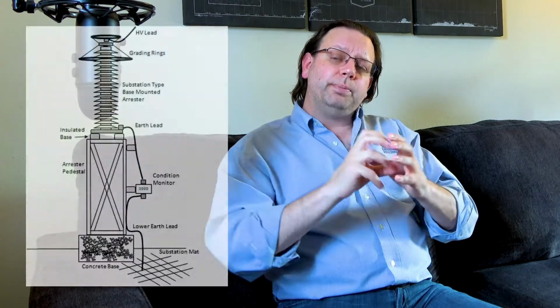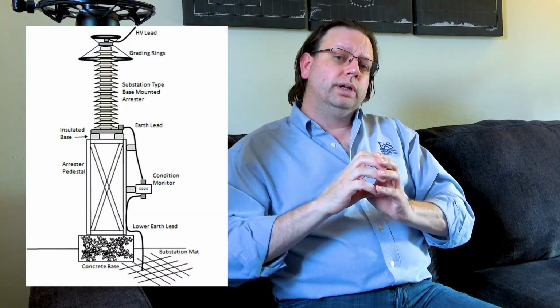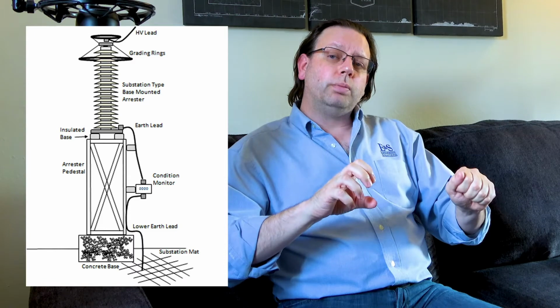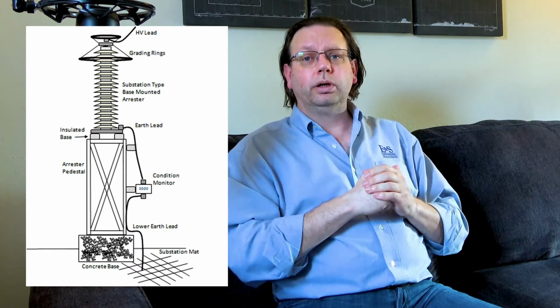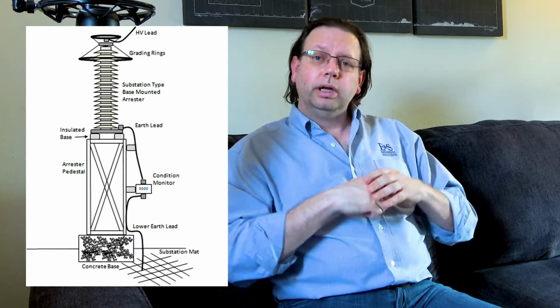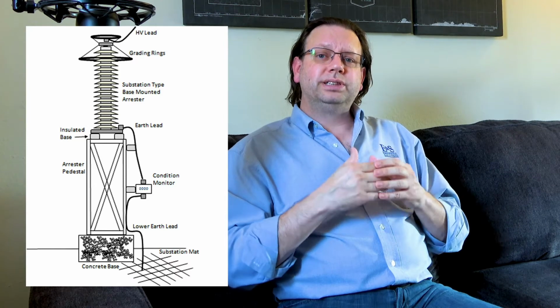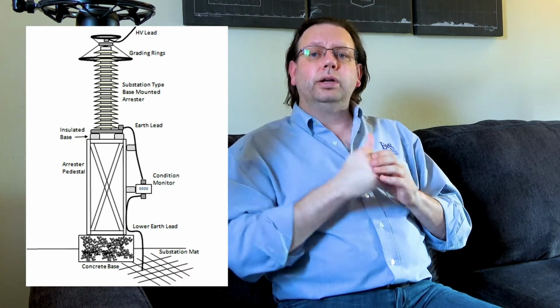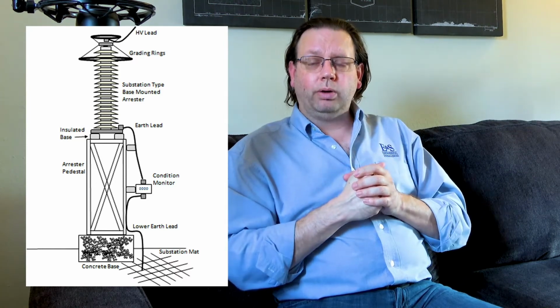So that clamp-on meter, when we're in continuity mode, can tell us whether or not we have problems that our 2-point meter will not tell us. Now let's take another example. Let's take a lightning arrestor for one of our incoming power lines.